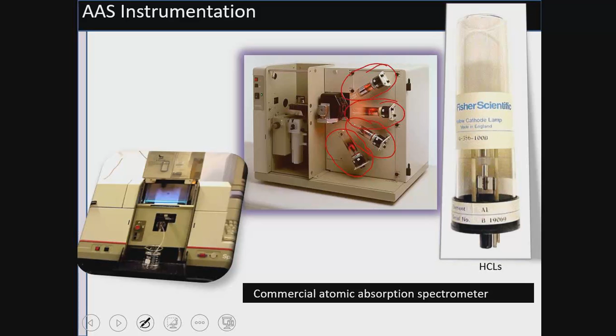Now we come to the first part of atomic absorption instrumentation, that is hollow cathode lamp. Hollow cathode lamp is a glass tube that contains a hollow cathode at the center, and this hollow cathode is made up of the material that is to be analyzed. If the hollow cathode is made from a different material, then it is coated with the material of the analyte. This hollow cathode is enclosed in a glass shield, and by the side of this glass shield an anode is placed.